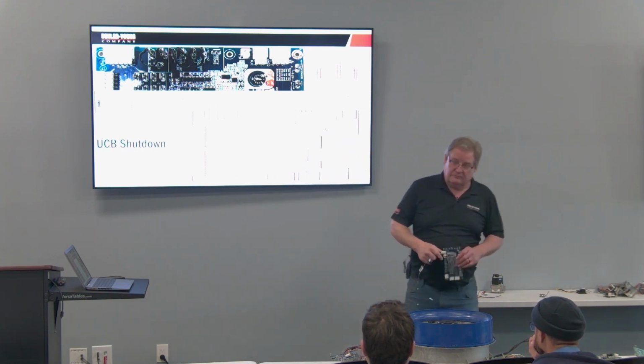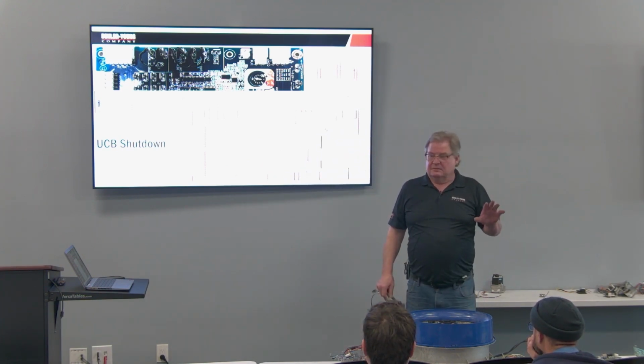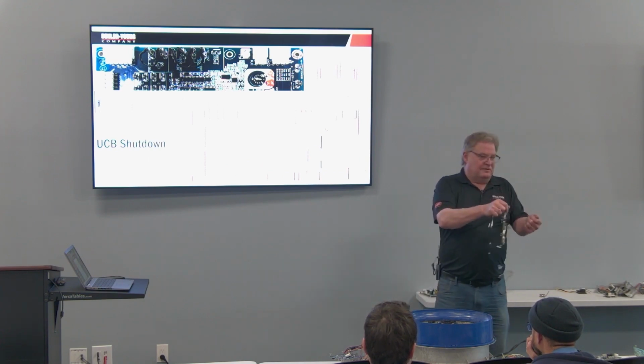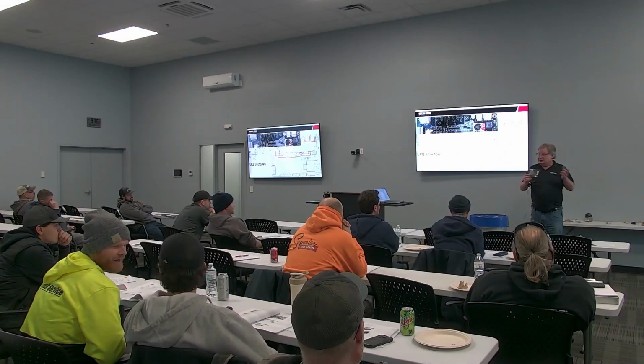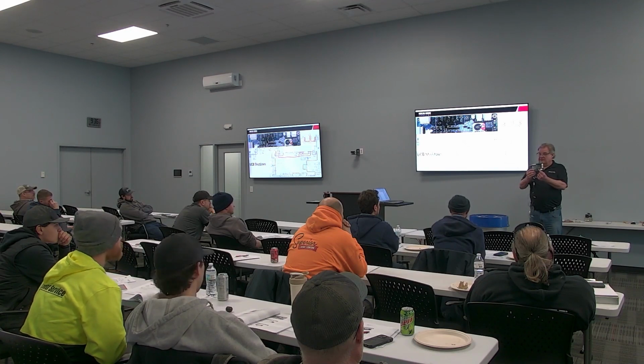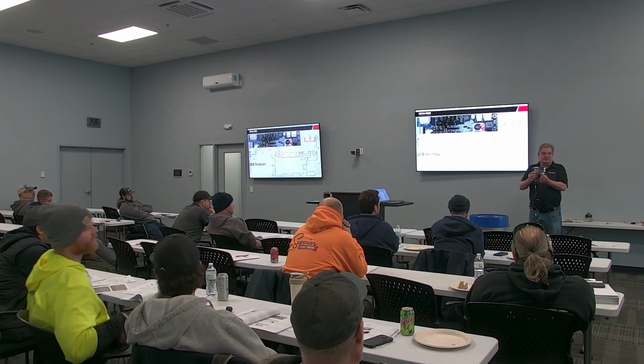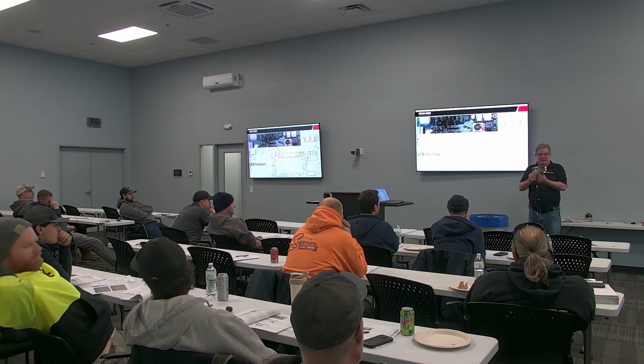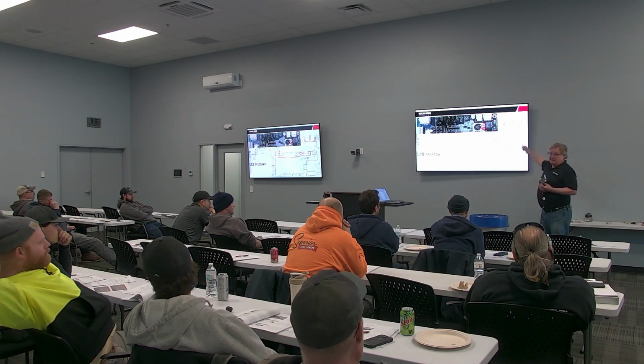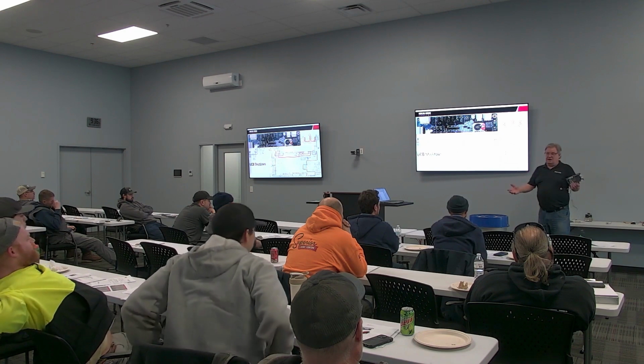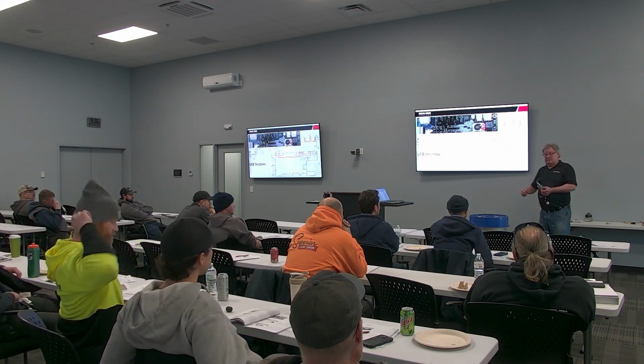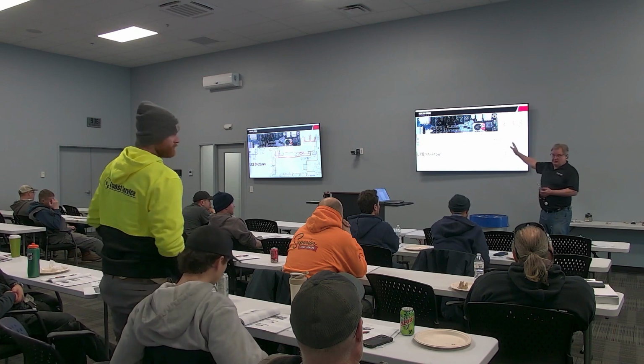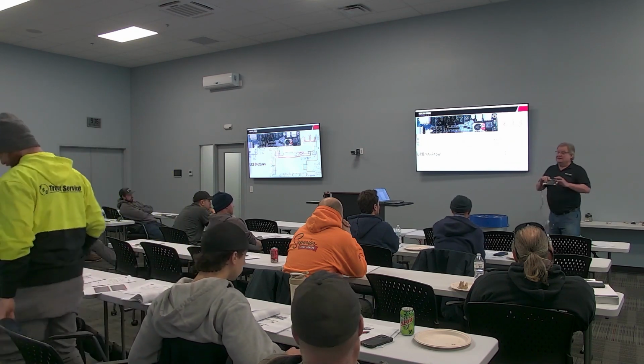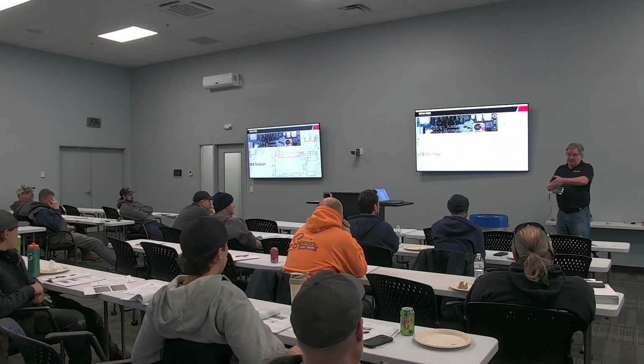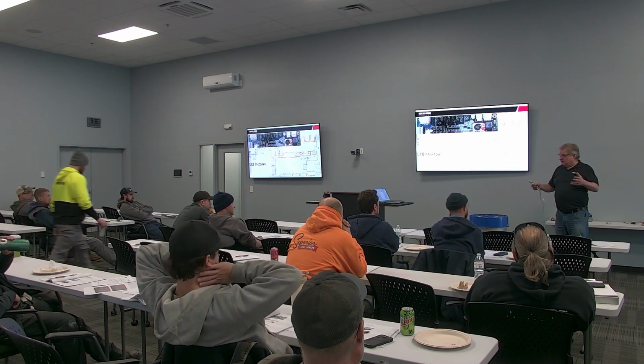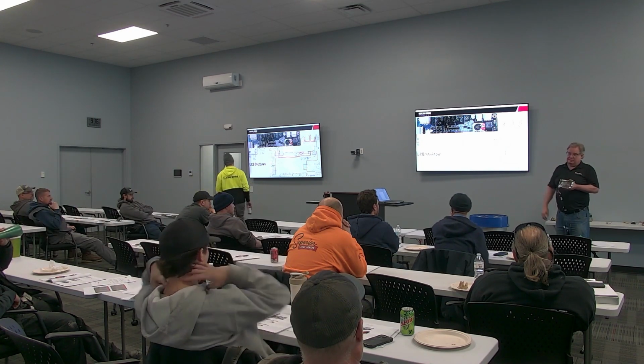So, if I've got no 24 volts, you come up on the unit, I go to RC, I've got no 24 volts. The first place I'm going to check starts right here. Go through these jumpers here. Is my smoke detector open? I'm going to go through all these. And then from here, the next thing is the safety in the motor. So if the unit's just sitting there off, go look at the motor. Do they have the red wires? If you don't have the red wires, it doesn't have a safety circuit. So if you've got the red wires, check to see if they're open. That motor might not be bad; maybe they overamped, they faulted out, they shut off, they kill 24 volts to the unit.